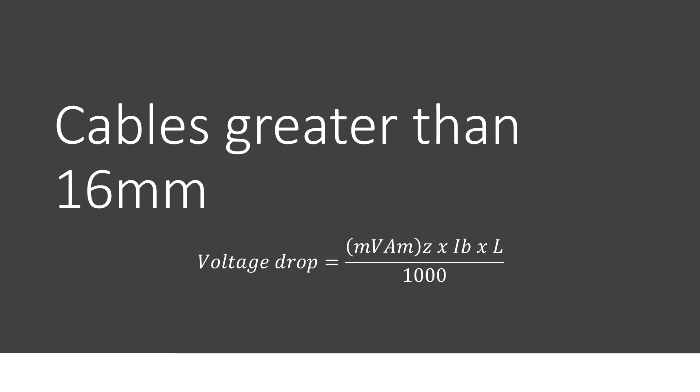So the equation becomes voltage drop equals millivolts per ampere per meter Z multiplied by design current, multiplied by length and then divided by 1000.